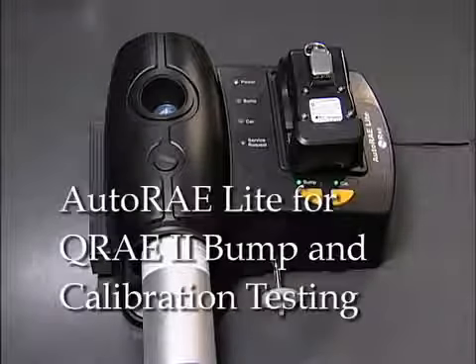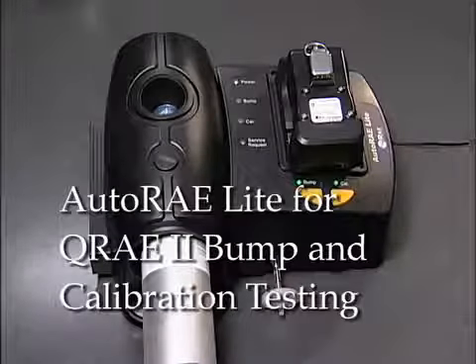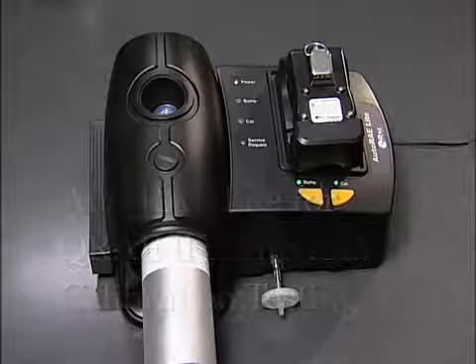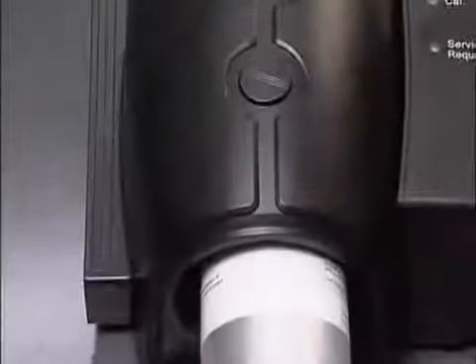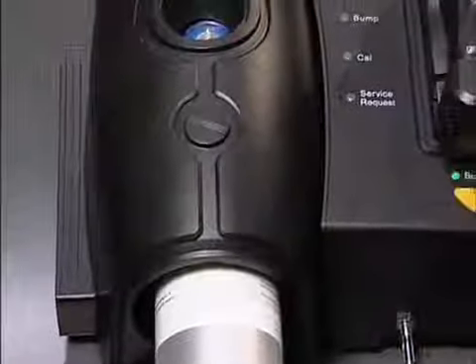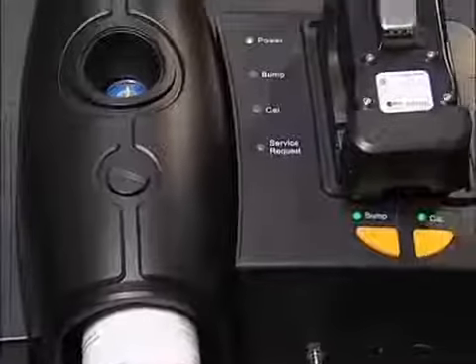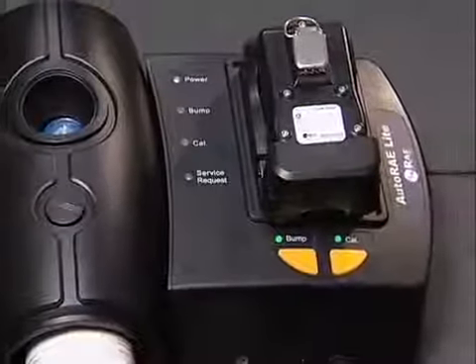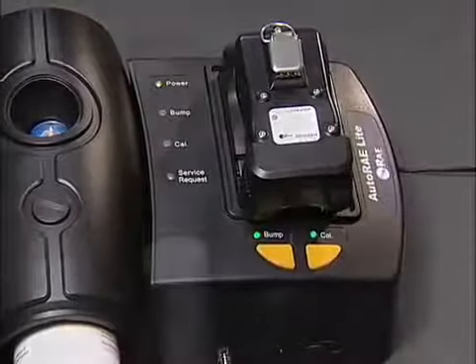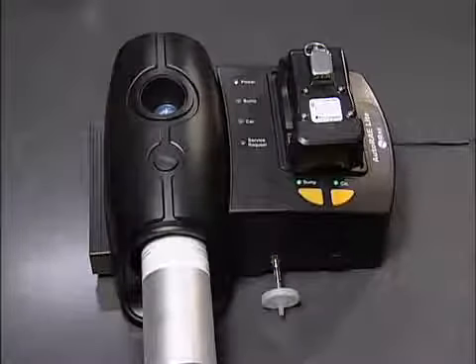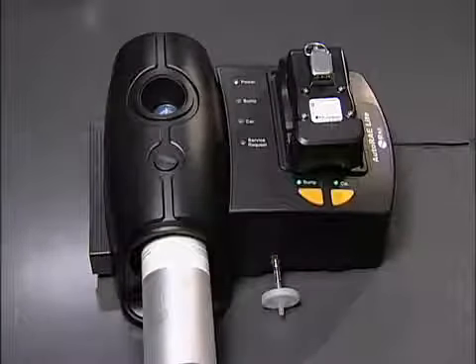The AutoRAE Lite for QRAE II is an automated bump testing calibration station designed for performing bump test and calibration of the QRAE II monitors. It can be used on a tabletop, a flat surface, or mounted on a wall. In addition, it can be powered by either an AC adapter or 4 alkaline C-cell batteries.